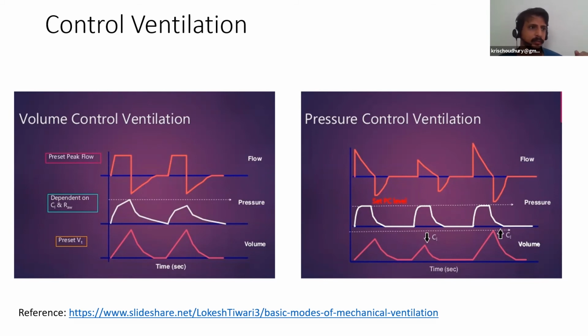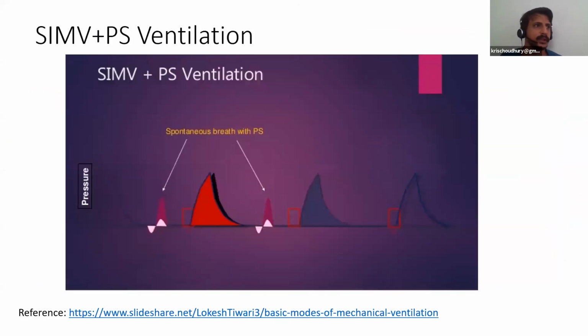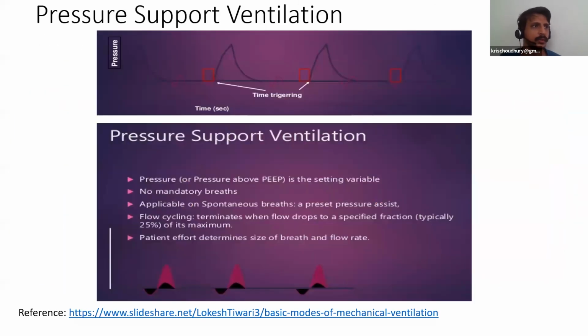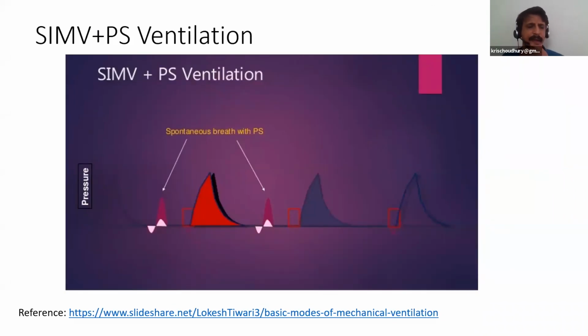If you want to go beyond this mode, like maybe an SIMV mode or an assist mode, you would need pressure sensors over here that typically sense around 1 centimeter of H2O pressure. And in engineering, we know that if you're trying to measure something, its least count needs to be around 1/10 to 1/5 of what you're measuring.